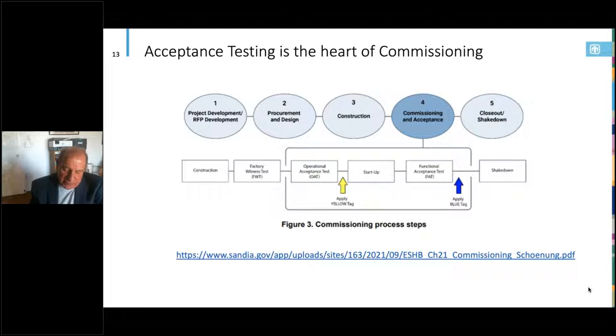And shakedown is kind of a special thing. That's basically when you turn the power off, or try to implement or synthesize something bad happening, to see that your system shuts down the way it should shut down, and then comes back online the way it should come back online.